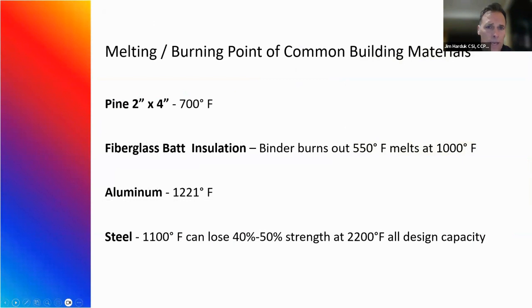And to put that in perspective, if we look at the melting and burning point of a few common building materials, we know that a pine 2x4 will ignite at about 700 degrees Fahrenheit. Fiberglass bat insulation, the binder will burn out of the fiberglass insulation at around 550 degrees, making the insulation very friable and fragile. And then at 1000 degrees, bat insulation will melt completely. We also know aluminum melts at around 1221 degrees Fahrenheit, and at 1100 degrees Fahrenheit, steel can lose about 40 to 50% of its strength. And at about 2200 degrees Fahrenheit, steel will yield all of its design capacity. So you can see that the test method that we subject these firestop systems to is pretty severe. These temperatures are pretty extreme. Next slide, please.